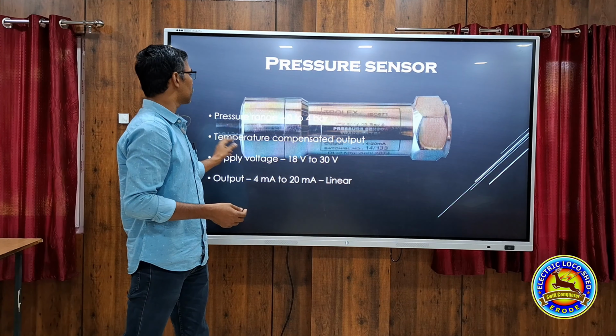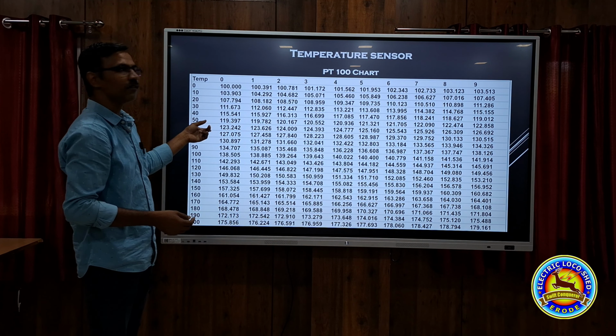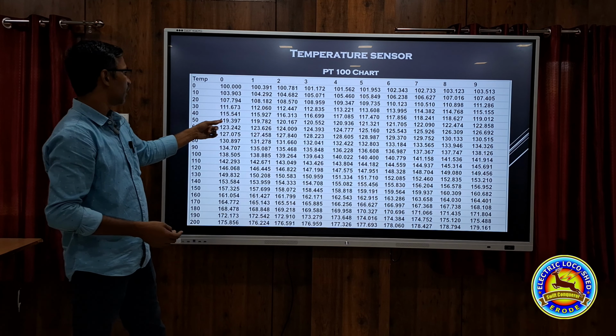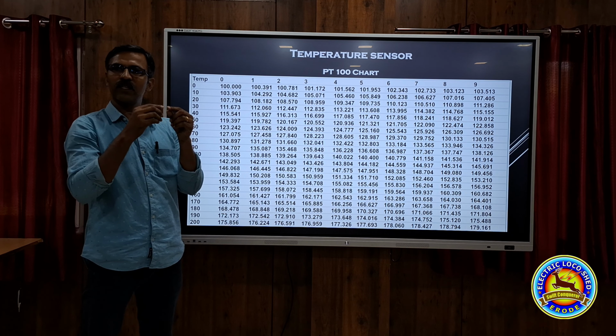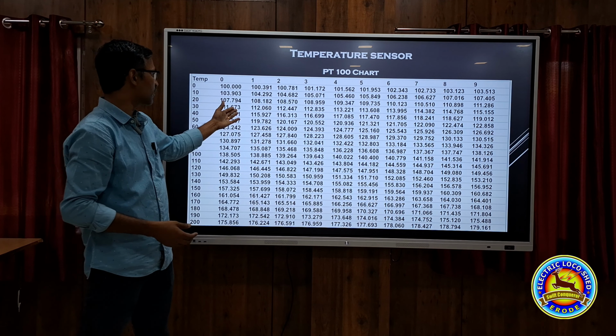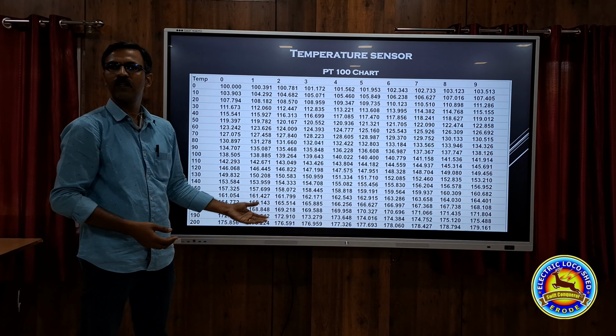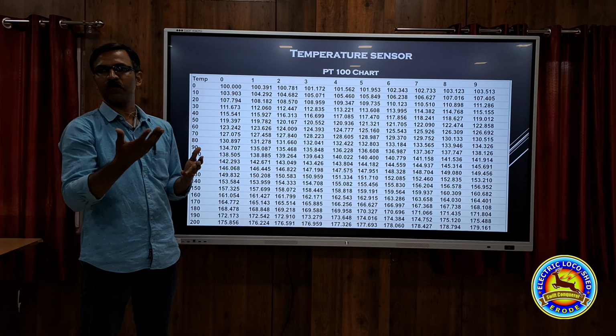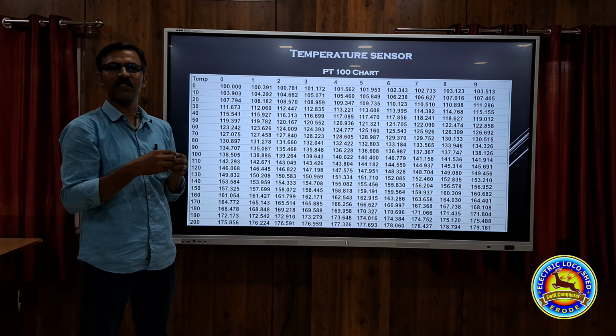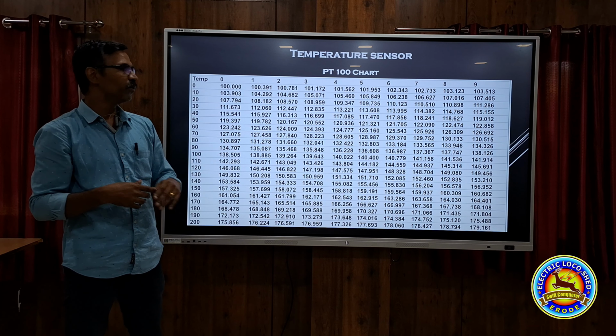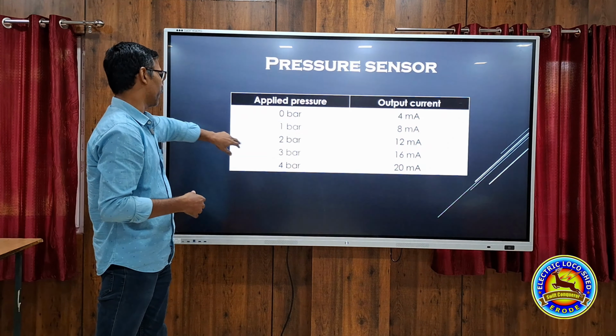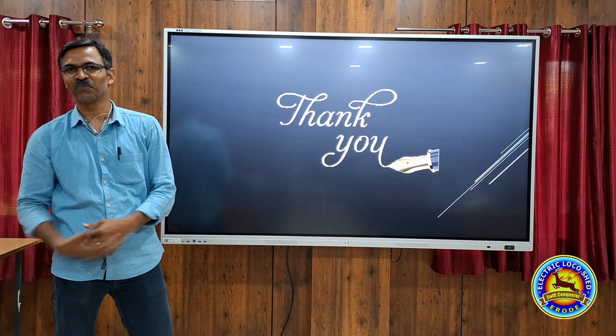If a loose contact comes, what happens? This is the PT100 chart. If a loose contact happens, the resistance value will increase. If the resistance value increases, the system will detect it as a higher temperature. So a loose contact in the temperature sensor is a big issue that will create unwanted tripping. That's all. Thank you.